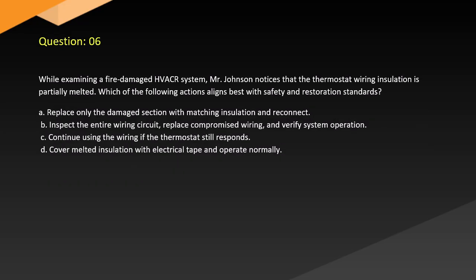Question 6. While examining a fire-damaged HVACR system, Mr. Johnson notices that the thermostat wiring insulation is partially melted. Which of the following actions aligns best with safety and restoration standards? A. Replace only the damaged section with matching insulation and reconnect. B. Inspect the entire wiring circuit, replace compromised wiring, and verify system operation. C. Continue using the wiring if the thermostat still responds. D. Cover melted insulation with electrical tape and operate normally.